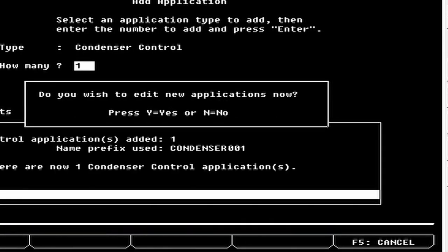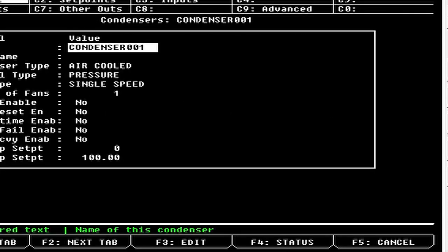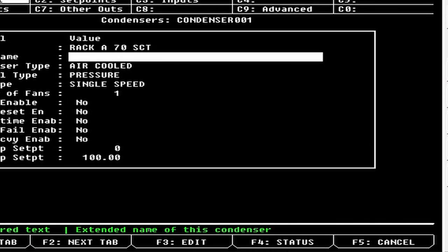Now we're going to change the name. I usually make it something like 'Rack A 70 SCT' — SCT meaning Saturated Condensing Temperature at 70 is my target. You can call your long name whatever you want: floating head pressure, Rack A, whatever.